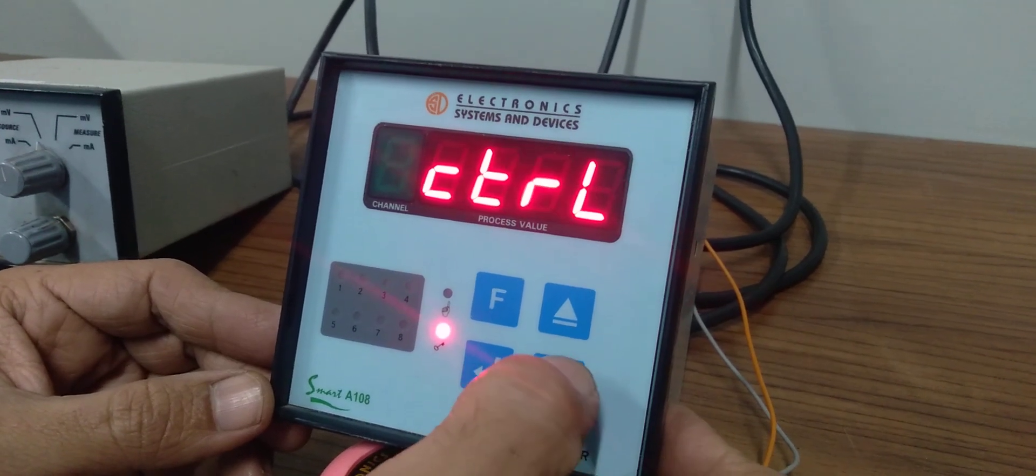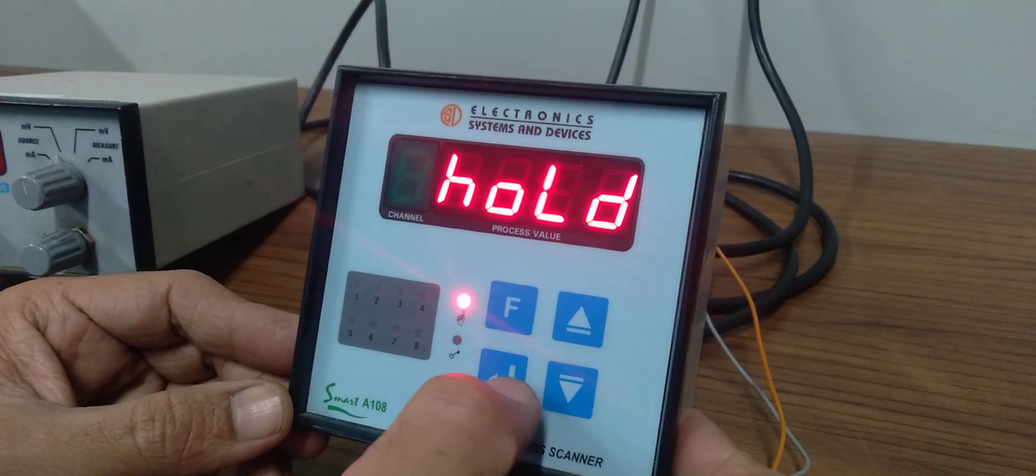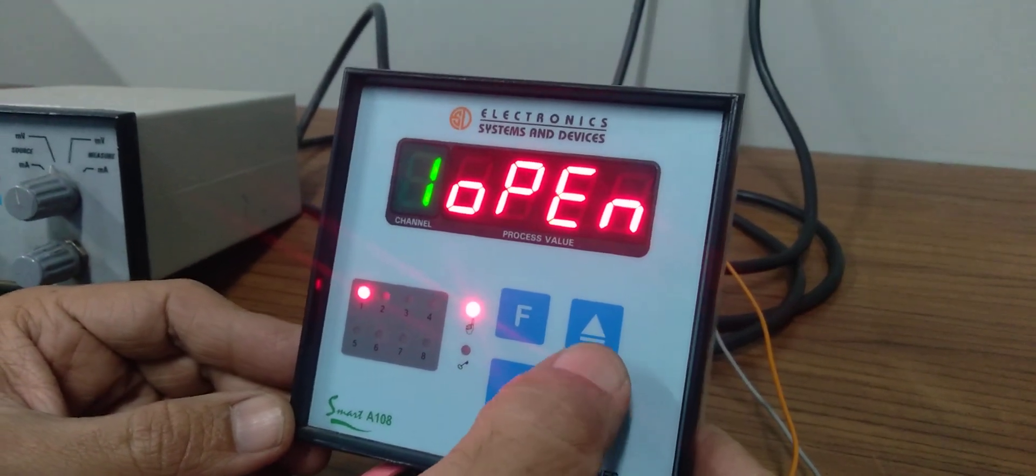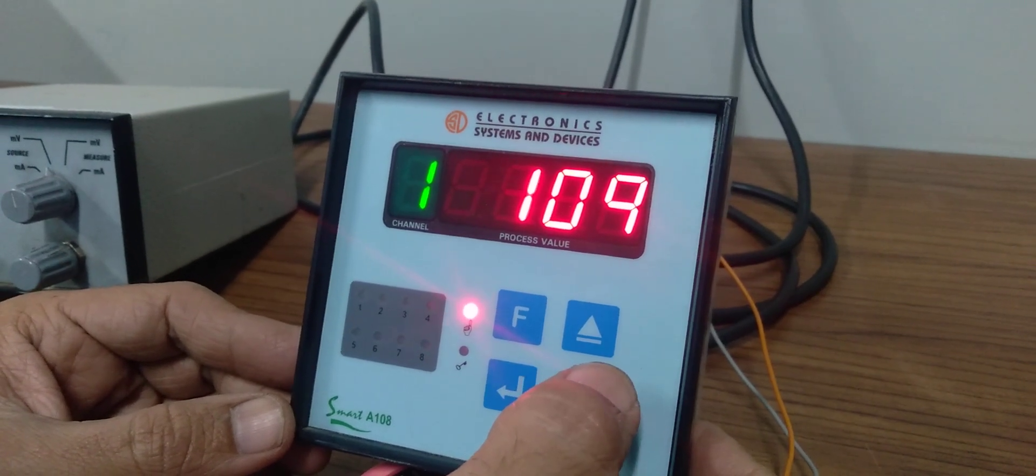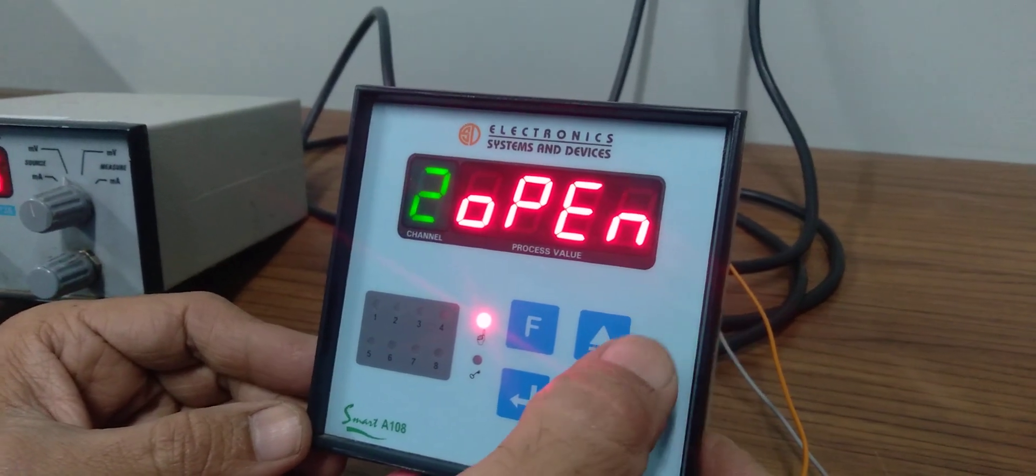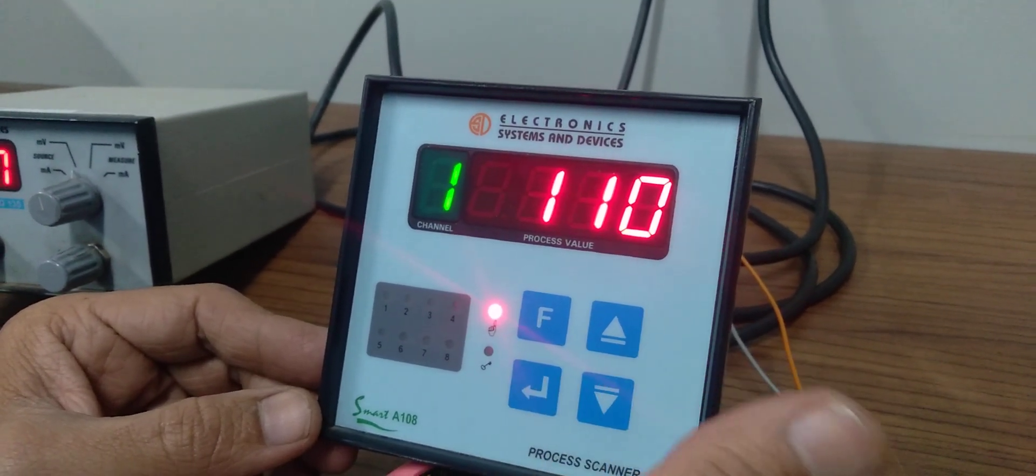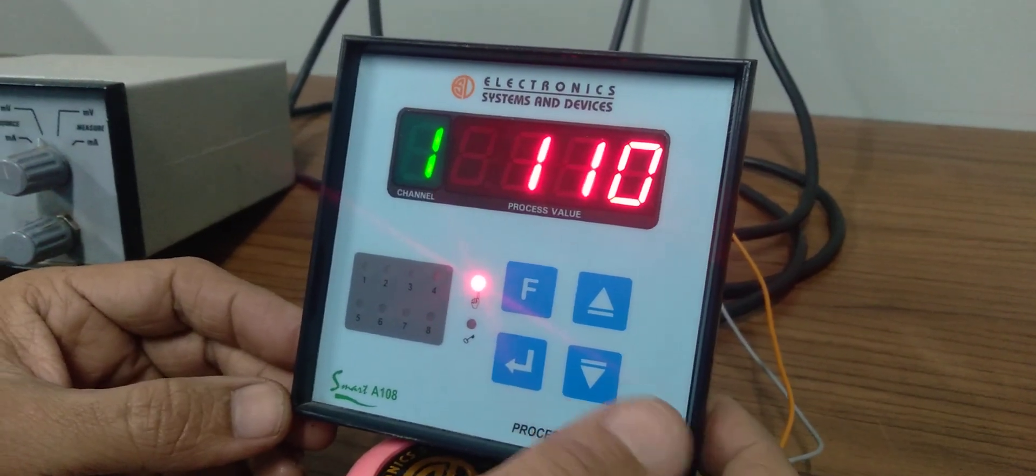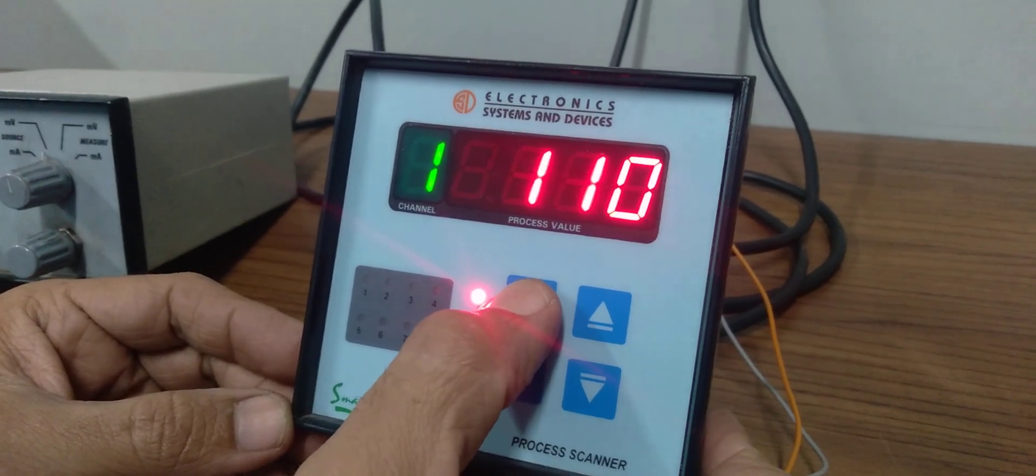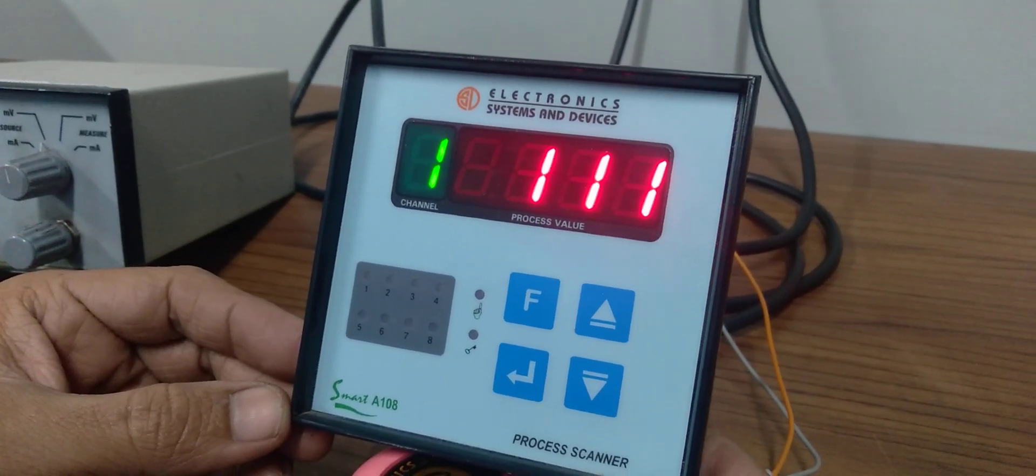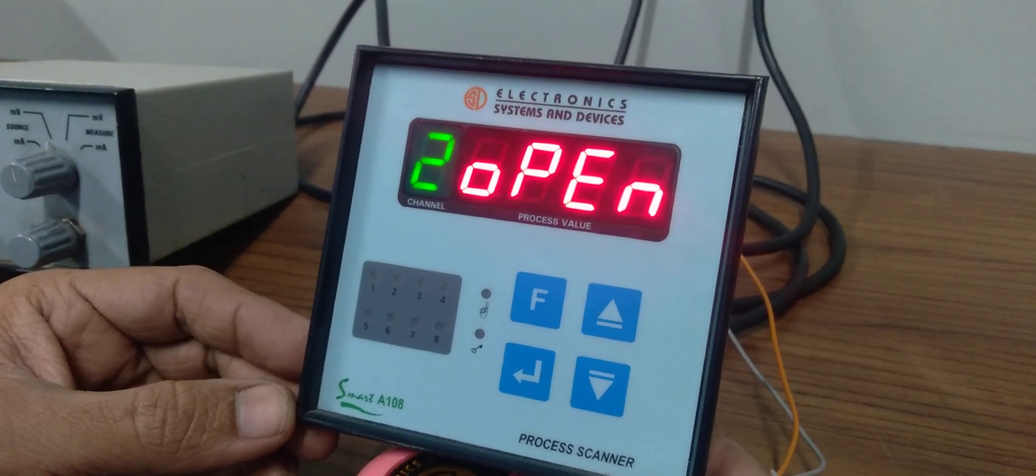We'll see the hold mode first. If you press enter here, it will show one particular channel. If you want to see another channel, press the increment key and it will go to the next channel and stay on that channel. This particular LED shows that it's in hold mode. Otherwise, in standard auto mode, each input keeps scrolling at a particular time. Now it's automatically going to the second channel, then the third channel.